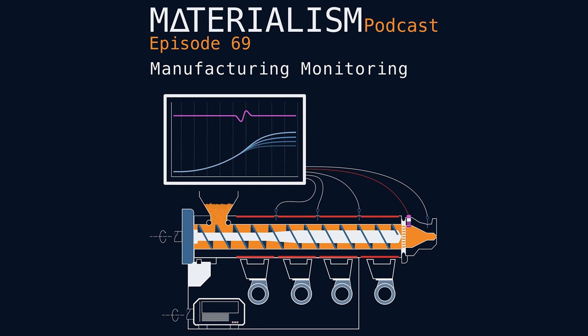The problem they were having was an inconsistent flow. That would cause jamming further down the line. If you want to think of it like spaghetti noodles coming out of the end of a machine, there's a knife coming around, cutting it off, and consistently, so it doesn't get gummed up on the tip, the flow needs to be controlled. So we used one of our temperature controllers and high speed controllers to solve the problem. It actually did two things. It controlled the motor drive, which was in this case a big 200 horsepower drive, and within 5 milliseconds it could change or adjust to pressure changes. So if there was any problem with the feed of the material coming through, it would immediately adjust to it and provided a more consistent compound and more consistent product.